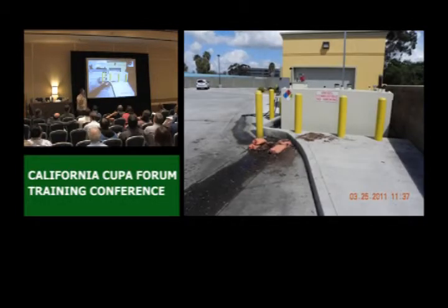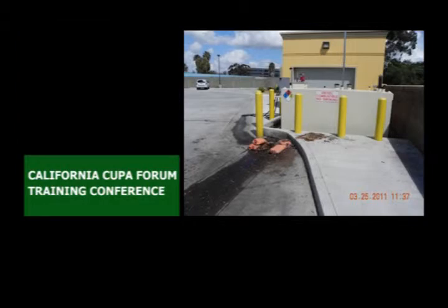They need a safe drain. They just need something. They need to block this drain, because that's way too close. Way too close for the loading. That double-walled tank, way too close. I don't care what kind of spill kit they have, unless that spill kit is jammed into the drain.